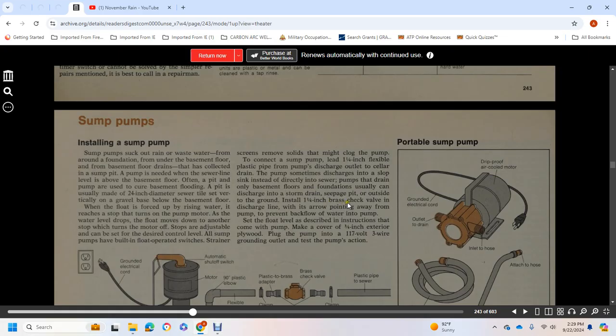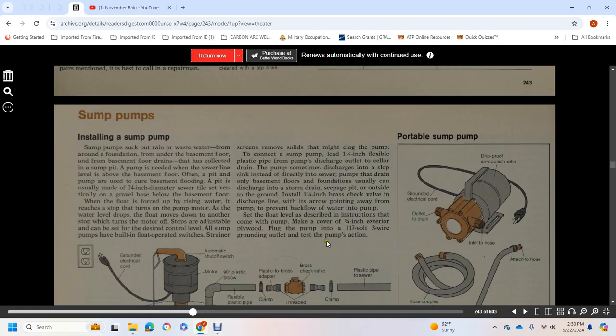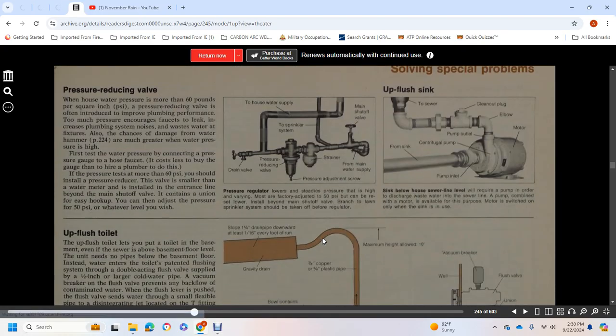Install a 1 1/4-inch brass check valve in the discharge line, with the arrow pointing away from the pump, to prevent backflow of water into the pump. Set the float level as described in the instructions that come with the pump. Make a cover of 3/4-inch exterior plywood. Plug the pump into a 117-volt, 3-wire grounding outlet. Test the pump's action.